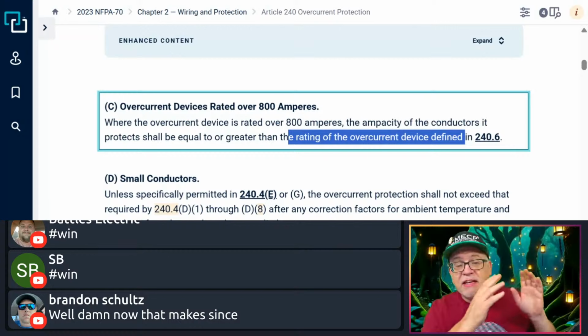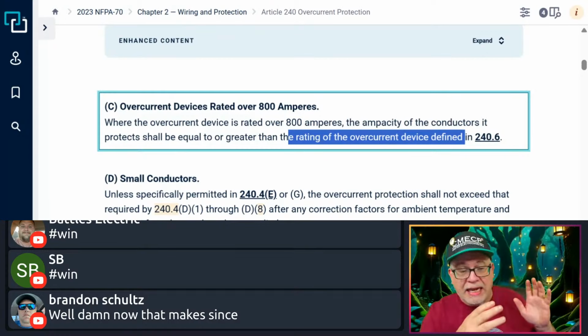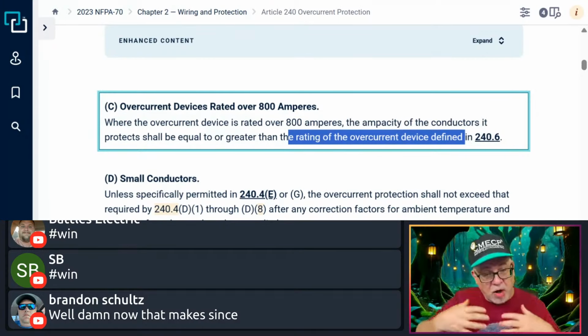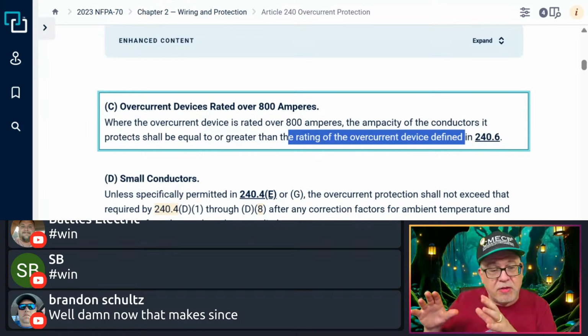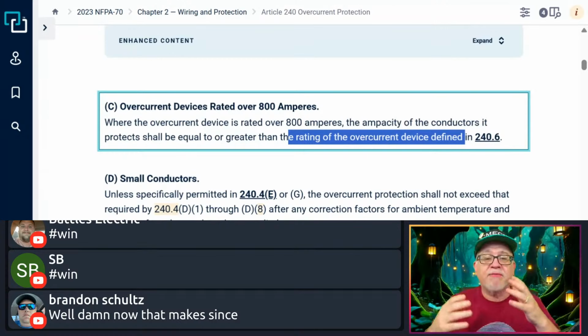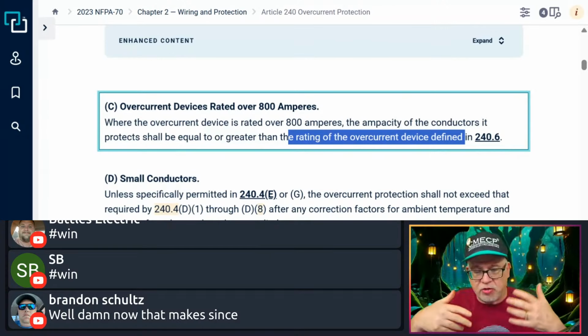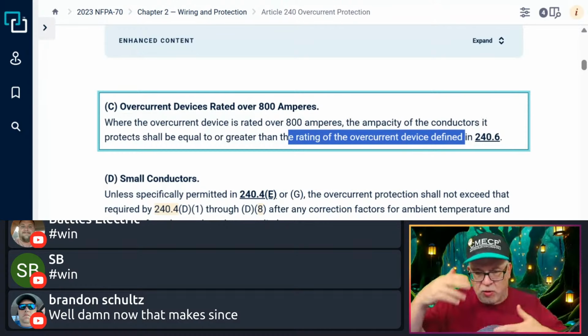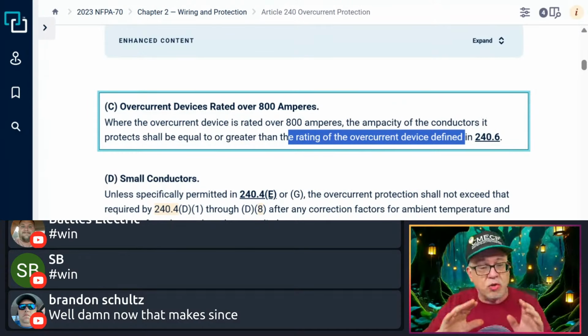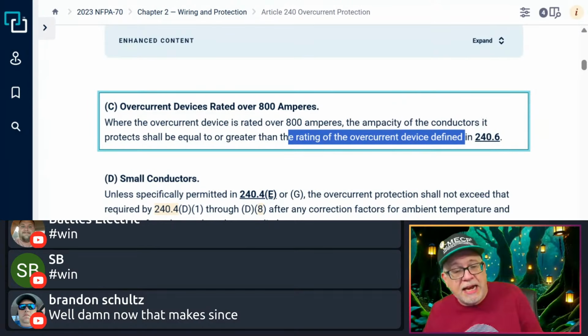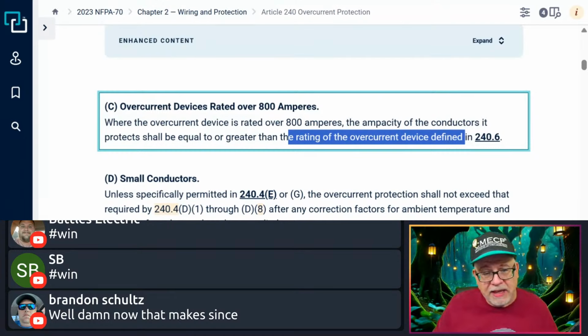And the utility folks tend to do some weird and wacky stuff. But from our perspective, once we get to the main breaker and we get downstream, we follow those rules to protect the conductors in 240.4, A, B, C, and D, and those type of things. And this is how you would do it if you're dealing with over 800 amps. Does that make sense? Hopefully that makes total sense to you. And that's what we get out of that example.